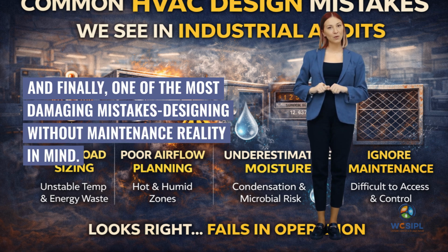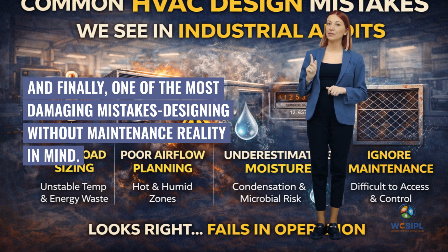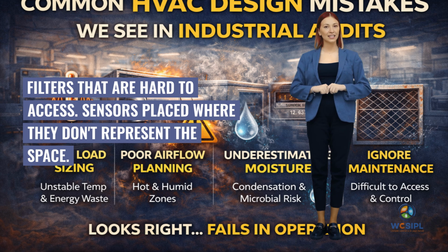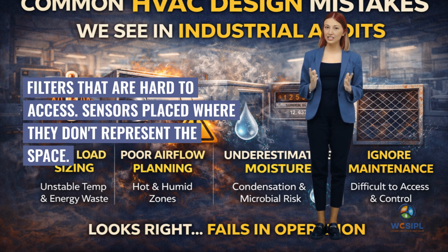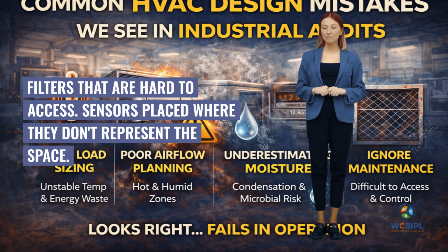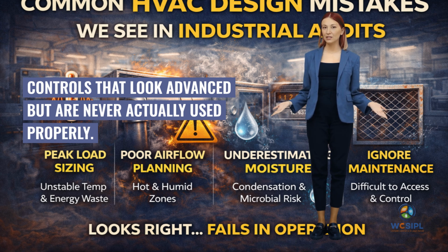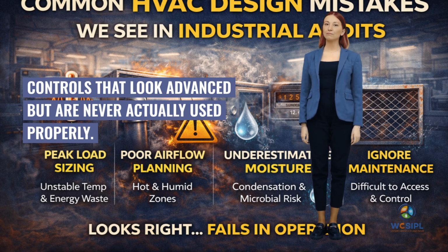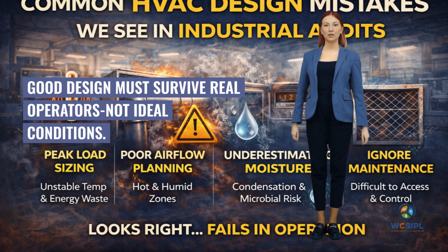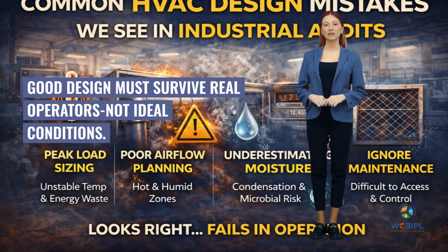And finally, one of the most damaging mistakes: designing without maintenance reality in mind. Filters that are hard to access, sensors placed where they don't represent the space, controls that look advanced but are never actually used properly. Good design must survive real operators, not ideal conditions.